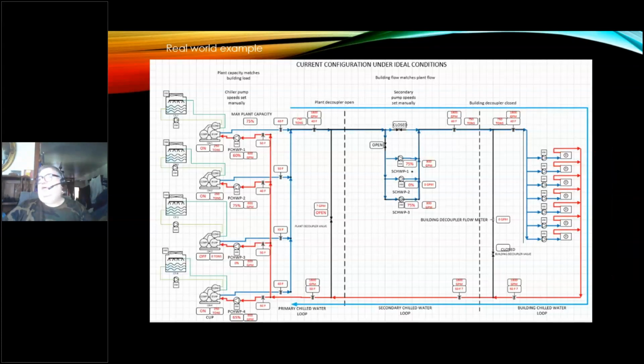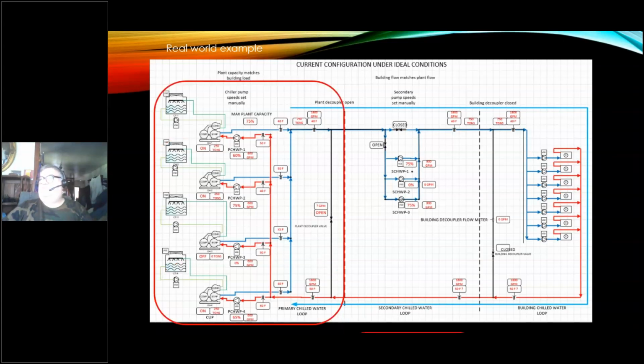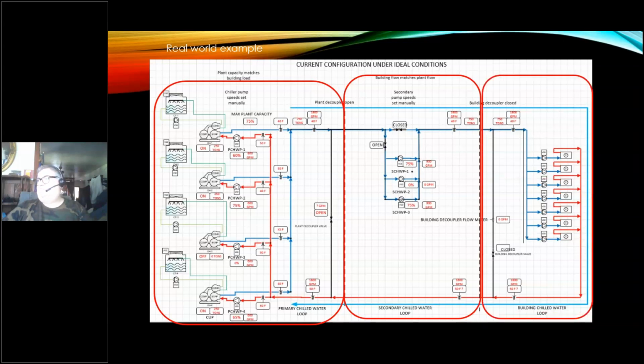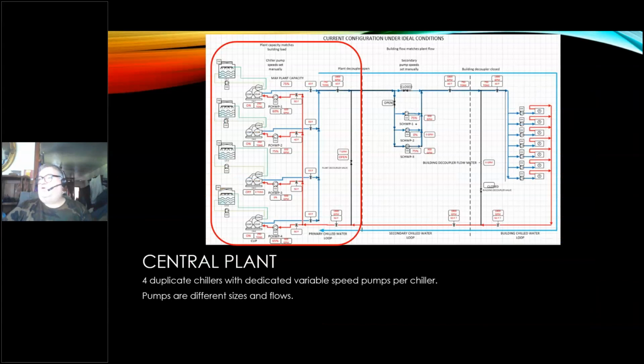Okay. Now, this is probably the biggest nightmare. This is actually a system of 3 separate sections: the central plant, the secondary to transfer from the central plant into the building, and the building by itself. The pumps transfer the chilled water out of the plant to the building. But I've got in the central plant 4 duplicate chillers, duplicate variable speed dedicated pumps, but the pumps are all different sizes and flows. Somebody got the wild idea to get the cheapest pump they could find. They came up with a pump that actually pumps higher than what the design required and put it in. And so now I've got this headache where if I'm running this chiller, I've got to run this flow, and nobody knows how to do this.